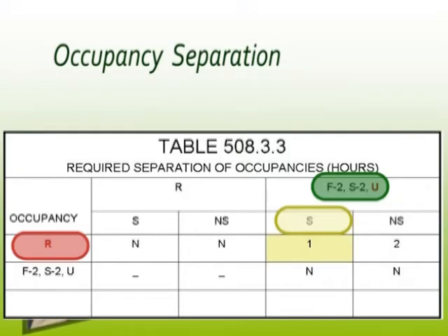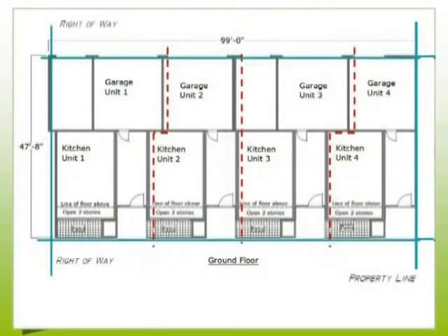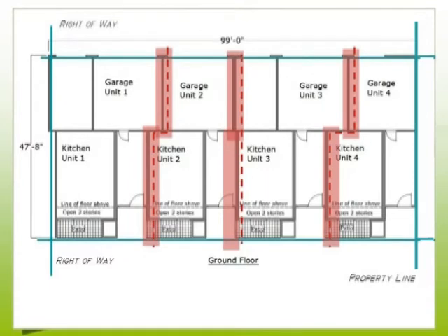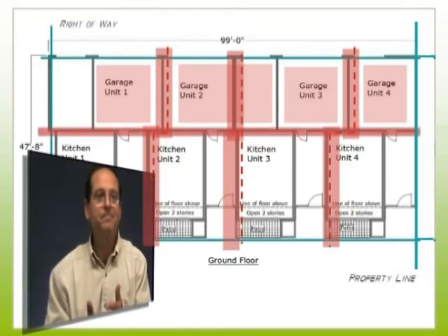So what this table is telling us now is that separation from the garage from the floor ceiling up to the next unit, or the wall to the unit, those have to be 1 hour. So now what we've done is we've just now identified 3 specific 1-hour assemblies: between dwelling units I should say, and the garage roof ceiling, and the garage wall to the dwelling unit. Let's move on. There's 1 or 2 more pieces here.